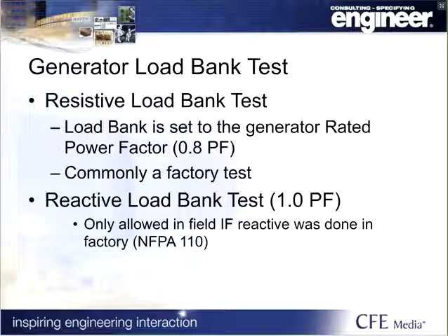In NFPA, it's just something you need to double check that occurs. Load banks are obviously one of the first things that you're going to need to get. The code, NFPA 110, requires that you do a reactive load bank test. I actually inverted these on the slide now that I'm looking at it. The first one is the reactive load bank test, which is going to be a 0.8 power factor. And typically that's done at the factory. However, you can do it in the field. I've had a couple of times where it just didn't get done at the factory, and we ended up pulling a reactive load bank out to the job site and testing it on site. Now, if you do a reactive load bank test inside the factory, then you are allowed to do a resistive load bank test in the field. And a resistive load bank would be at unity power factor, 1.0. And that's pretty much that.